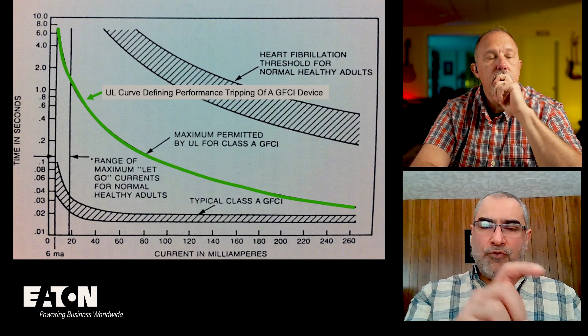I guess we call it instantaneous, but nothing is instantaneous. It doesn't have this curve that would say, okay, if I measure 20 milliamp, I'll be tripping quicker than when I measure 10 milliamp, for example. Right. And this green curve, the magic number is at 20 milliamp, it's 1 second. This is the maximum time because the equation is 20 divided by I to the power of 1.43. So if you have 20 milliamp, the maximum time a GFCI is allowed to wait to trip, or the maximum exposure time in this case, would be 1 second.